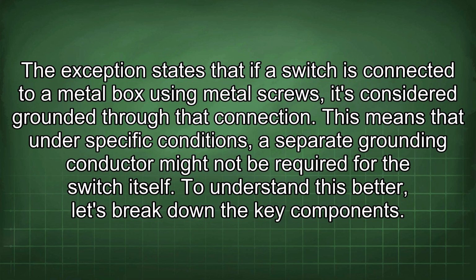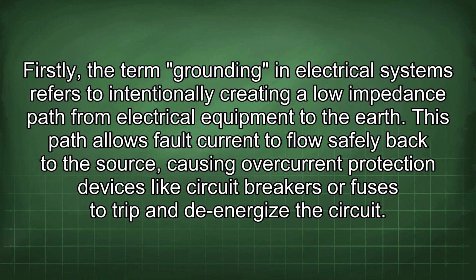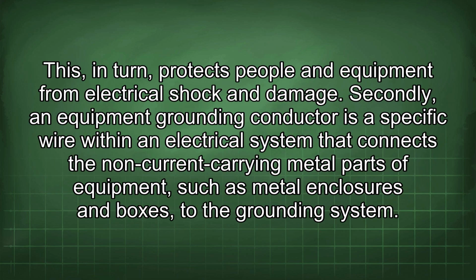To understand this better, let's break down the key components. Firstly, the term grounding in electrical systems refers to intentionally creating a low impedance path from electrical equipment to the earth. This path allows fault current to flow safely back to the source, causing overcurrent protection devices like circuit breakers or fuses to trip and de-energize the circuit. This, in turn, protects people and equipment from electrical shock and damage.